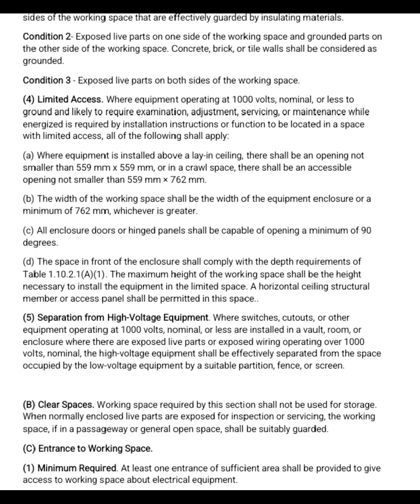Adequate openings. Minimum opening size must be 559 mm x 559 mm above ceilings or 559 mm x 762 mm in a crawl space. Working space width must be at least the width of the equipment or 762 mm, whichever is larger. Door panels must open at least 90 degrees. Front clearance. The space in front of the equipment must meet the requirements from the electrical code table. Ceiling structures in the limited space are allowed in the working area.